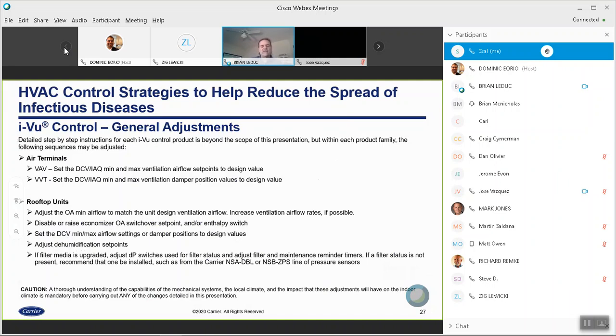The Taylor paper actually does, and it basically says that, as you probably know, you're trying to maintain a ventilation rate that is lower than design. There is some lag in how the DCV algorithms work, and the concern Taylor had was that if you had a space and there are only a couple of people in the space, it's likely that their output of CO2 might not be high enough to reach a level where the DCV algorithm would begin to bring the ventilation rate up to the design minimum. And obviously, it is known that person-to-person transmission can be very likely if someone's not wearing a mask, if they're too close to each other, all the social distancing stuff, easy for you to say. So their recommendation is basically reset your logic so that even your minimum IAQ DCV setting is what the design minimum is, right? So that's the recommendation there.